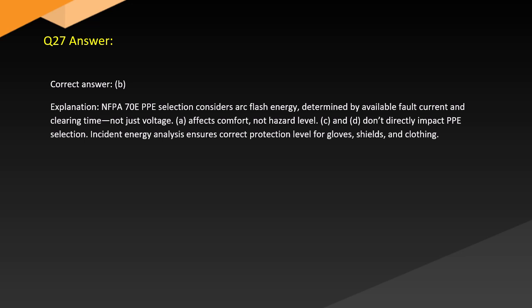Answer. Correct answer: B. Explanation. NFPA 70E PPE selection considers arc flash energy determined by available fault current and clearing time, not just voltage. A affects comfort, not hazard level. C and D don't directly impact PPE selection. Incident energy analysis ensures correct protection level for gloves, shields, and clothing.